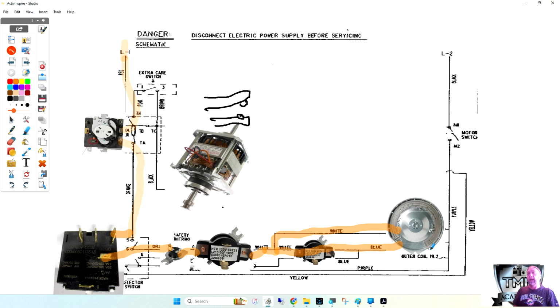So if you ever run across that, always sand and clean the terminals on the element if you're not changing the element, and make sure when you plug the wire on it's almost as tight as if the only way you're going to get that wire on is if you have to shove it on with pliers. Don't make it that tight, but that's what you're looking for - you do not want it to have any play or be loose, or it's going to burn up again. You're going to fix it and it's going to come right back, especially if you fixed a burnt one. So where do we go from here on the heater?